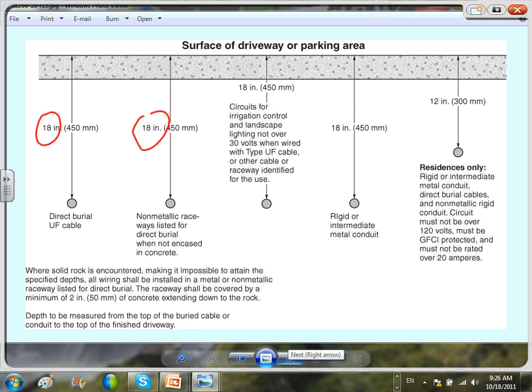Non-metallic, they lowered it, it was 18 anyway. So they lowered it a little bit, to 18 for rigid metal conduits if you have concrete right at the top of it. For residential, it continues to be 12 inches. If it's under a parking area or driveways or parkways and so forth. Any comments, guys, about this? Any comments about the depth? Really, the only depths you need to understand right now are 12 inches for GFCI protected, 18 inches for PVC for our project. And if you decided to use a UF cable, it's going to be 24 inches.